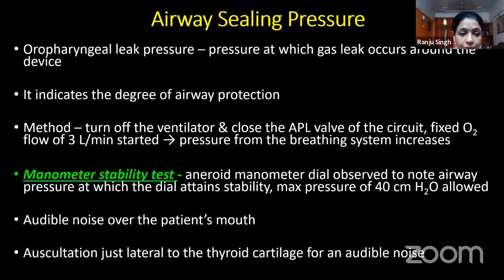And how do you do it? When you put the device in and connect the patient to a closed circuit or to a ventilator, to measure the oropharyngeal leak pressure, turn off the ventilator, close the APL valve of the circuit, and put the patient on 100% oxygen with a flow rate of 3 liters per minute. When you do this, the airway pressure in the breathing system will begin to increase. Carefully look at the manometer dial at this time. At a certain point, the airway pressure will increase and attain stability. Once it becomes stable and increases no more, that is the oropharyngeal leak pressure.